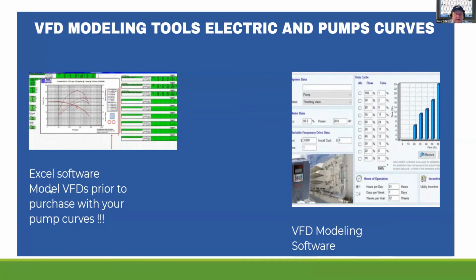Rob had the software he talked about, which was the Excel, which I highly recommend. If you're going to be selling VFDs and putting them in, you should be getting with your pump people, get the pump curve loaded in here, and look at those different set points before you stick the drive on. I've seen way too many VFDs put in that can't even bring it off of, maybe, run to 55 hertz. Then all of a sudden they stop pumping water and start cavitating. So this gives a modeling tool that helps you look in advance at what's going to happen, and maybe even if the guy needs to change the pump, he should be doing that in advance.